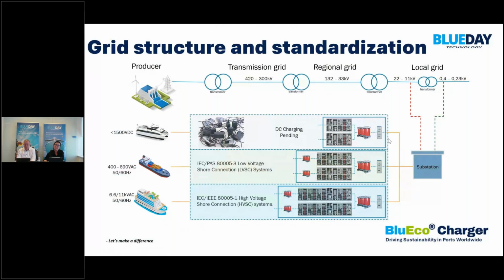Today, we have well implemented international standards for connecting various types of ships to the onshore power grid when it comes to AC power. This includes low voltage up to 690 volts and high voltage either on 6.6 or 11 kV, which we will explore in a later webinar. The upcoming IEC 80005 Utility Connection in Port Part 4, called DC Shore Connection System General Requirements, describes low voltage DC shore connection systems up to and including 1500 volts DC. It applies on board the ship and onshore to supply the ship with electrical power from shore.